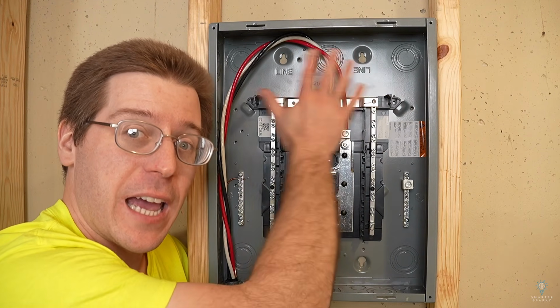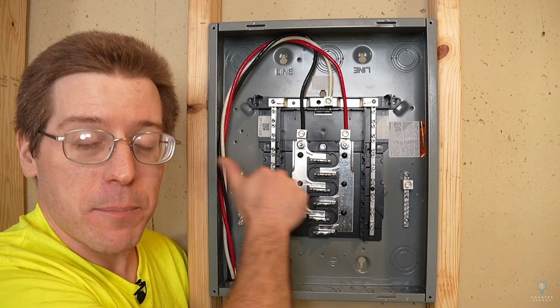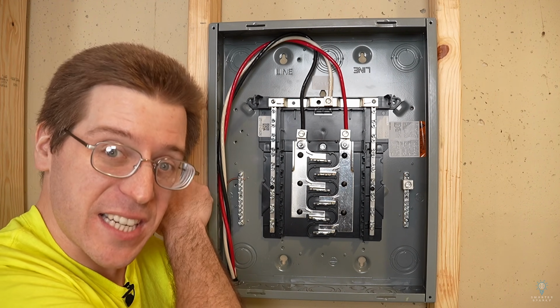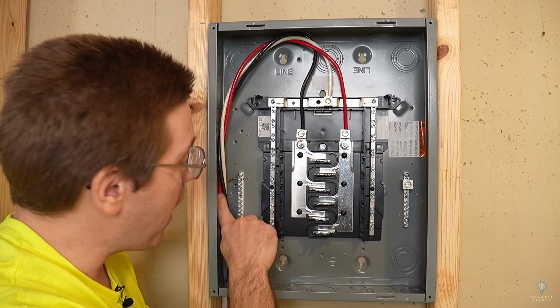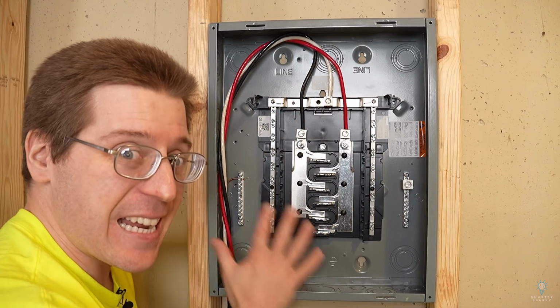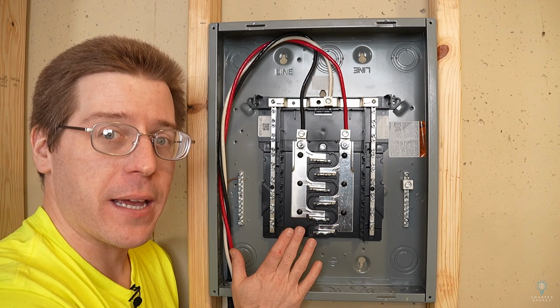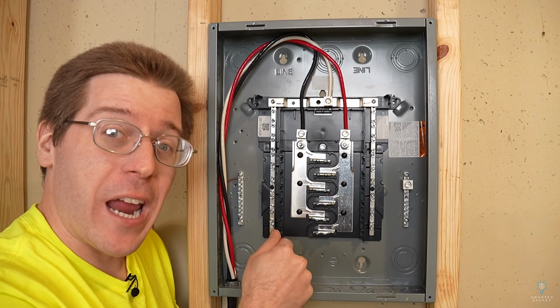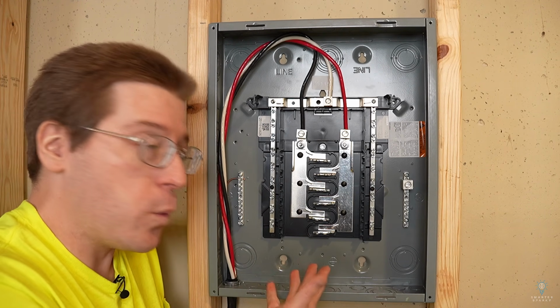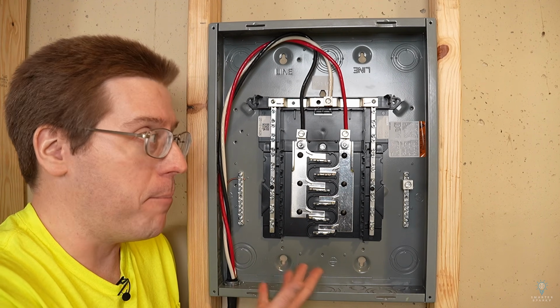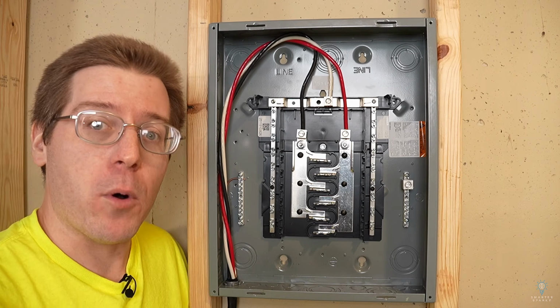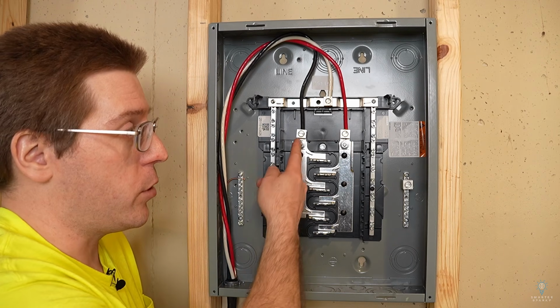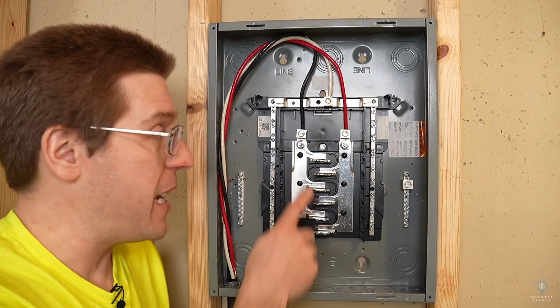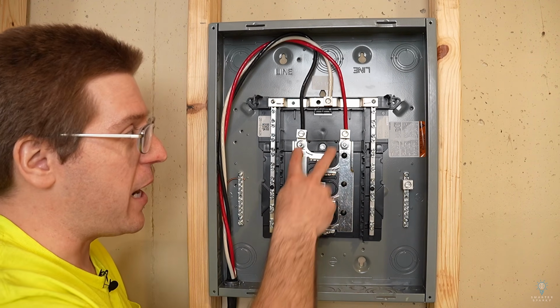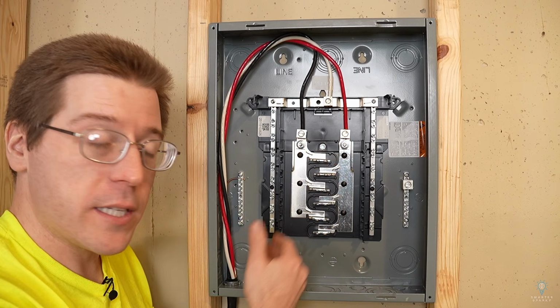Our circuit protection for this sub panel is going to be at the main electrical panel. We'll have a 60 amp circuit breaker over there that will protect this wire and the entirety of this electrical panel. So if this were a main breaker panel, could we still set it up as a sub panel? Absolutely, and there would be a couple ways we could do that. The first way is you could just go out and convert it to a main lug panel, and that would be just fine. You would get rid of that main breaker, put lugs here, and pass through.